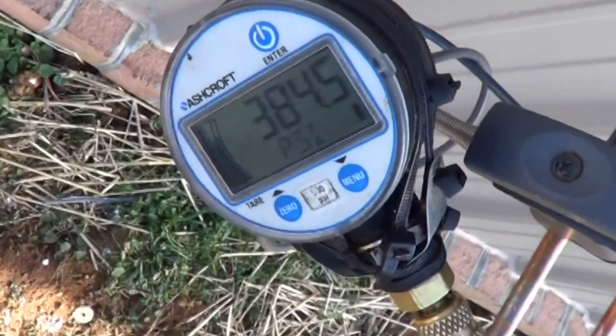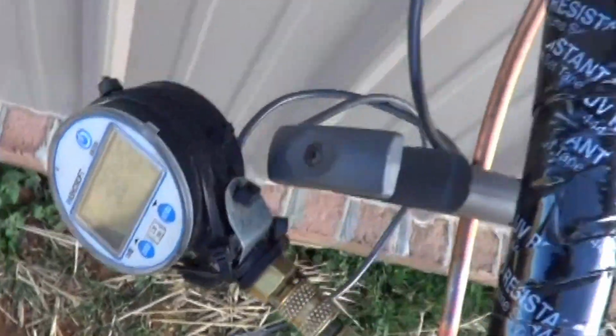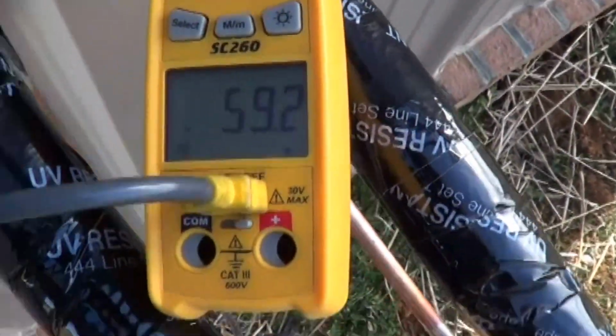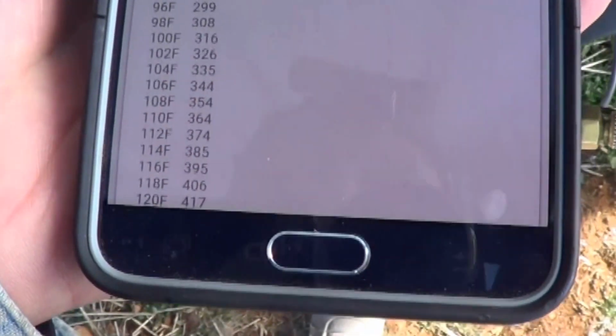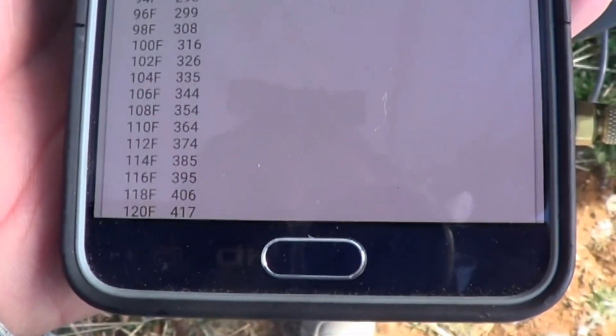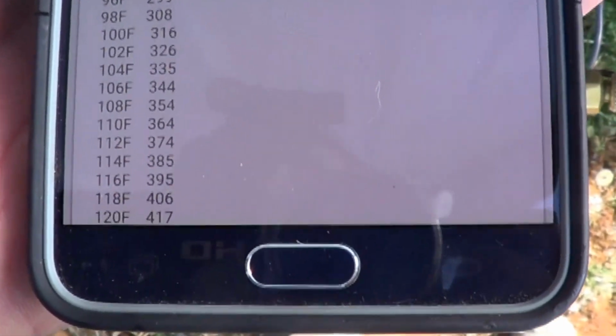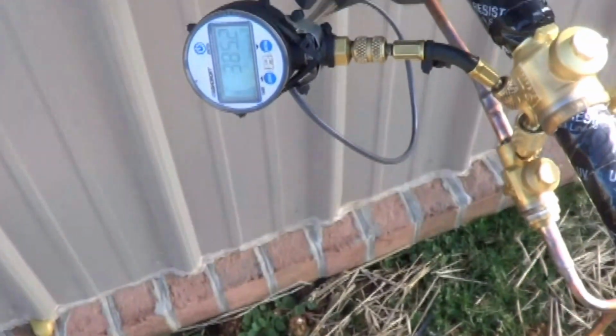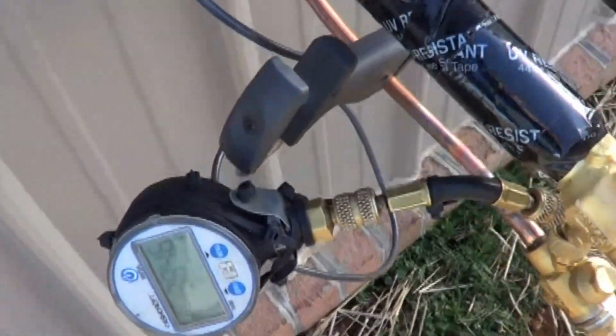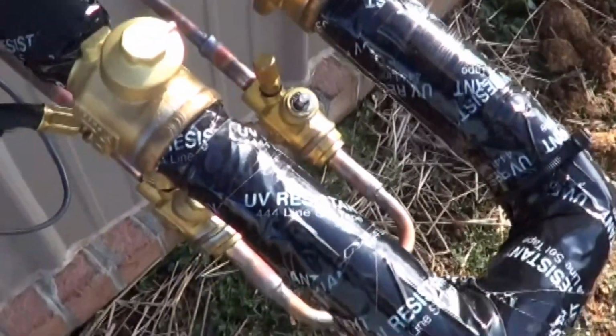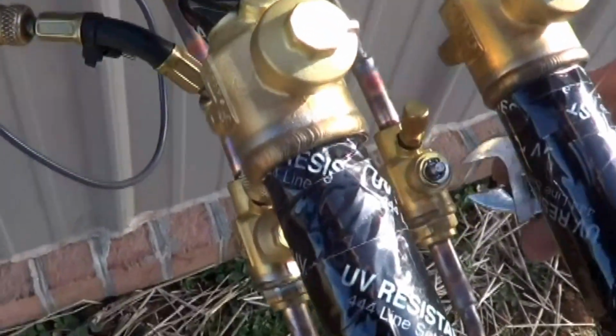So look at our subcooling. We got our pressures 384, 60 degrees. So we got 54 degree subcooling. And so we got an overcharge condition. So I'm just going to dump some refrigerant in the other circuit.